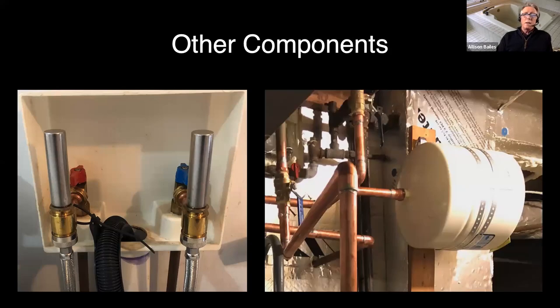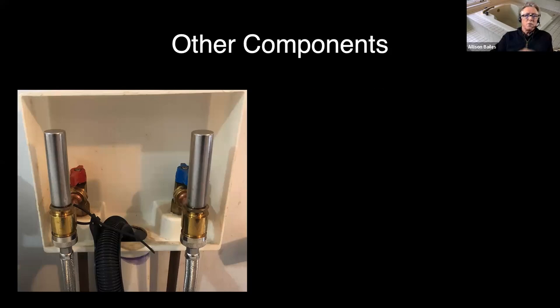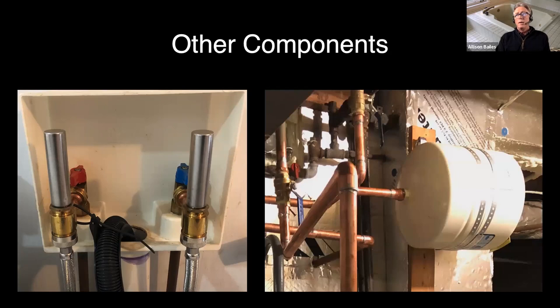Let me talk about this a little bit more. Water hammer happens because you get a pressure wave. When you have a valve that shuts off quickly, like in a washing machine or dishwasher, the water's coming in at a certain flow rate and boom, it stops. That puts a pressure wave that travels back through the line, and that's the banging that you hear. That's water hammer—it's that pressure wave traveling back through the line.